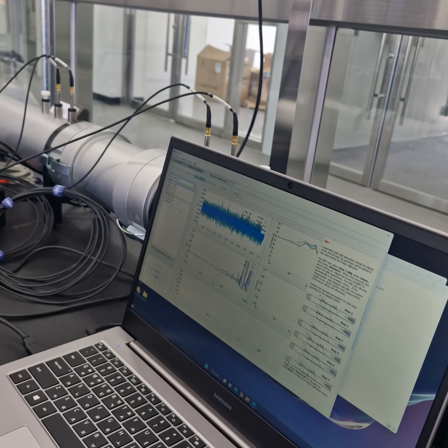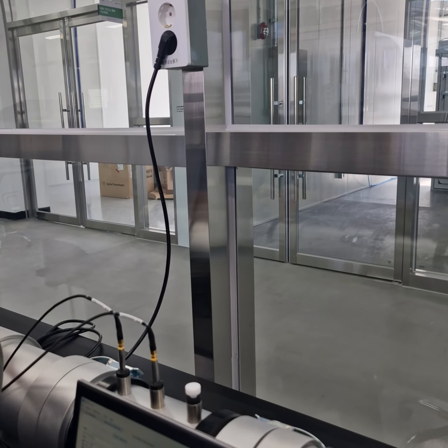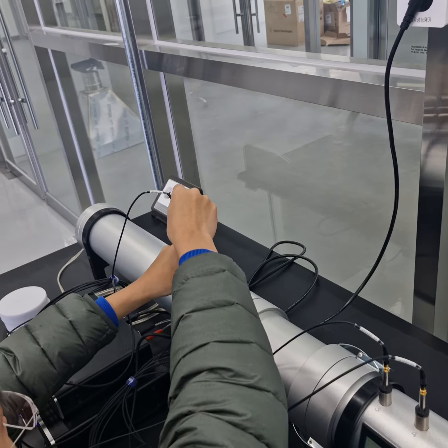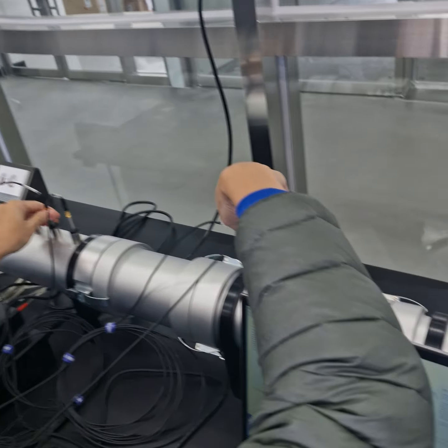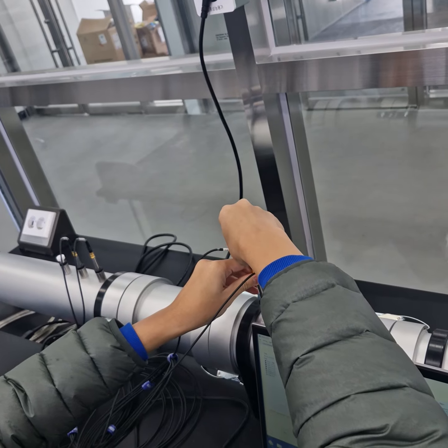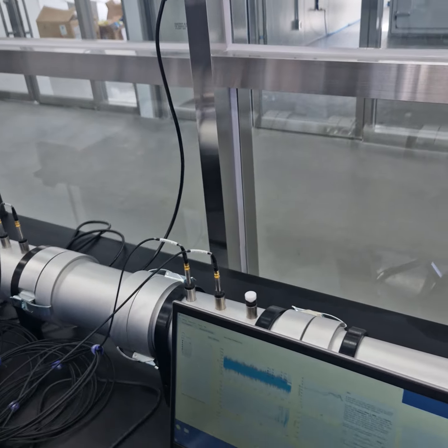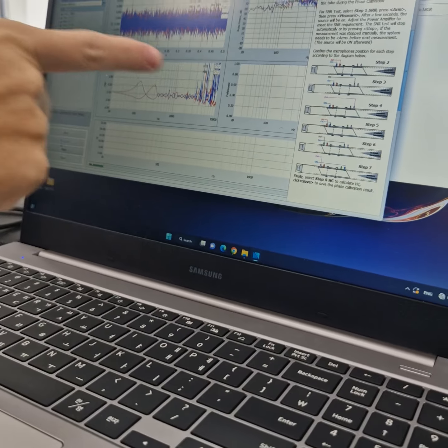After testing this one, we will test 3-1. So the first step is to switch it back. So 1 and 2 is still 1, 2, 3, 4, and then we switch 1 and 3. Yes, it's complicated. Okay. Then we start testing 1 and 3. This is still opposite.